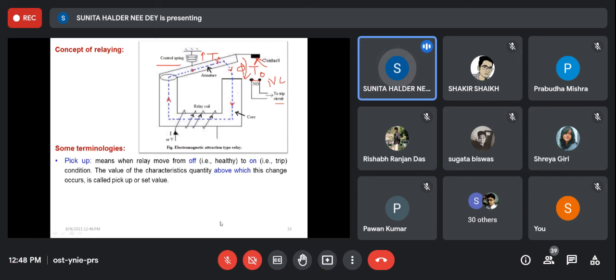So actually there are some terminologies related to that. There is one term, pickup. So what is the meaning of pickup? Pickup means that the moving portion of the relay tends to move. That means it is going towards closing. Pickup does not mean the relay is closed or has totally operated. Pickup means it has started its operation. That means the system current has started to go beyond its setting.